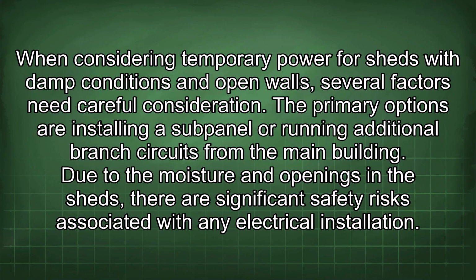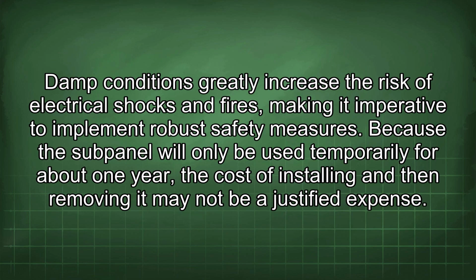When considering temporary power for sheds with damp conditions and open walls, several factors need careful consideration. The primary options are installing a subpanel or running additional branch circuits from the main building. Due to the moisture and openings in the sheds, there are significant safety risks associated with any electrical installation. Damp conditions greatly increase the risk of electrical shocks and fires, making it imperative to implement robust safety measures.